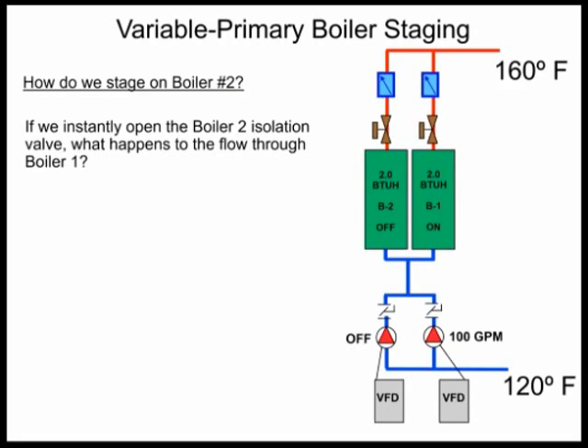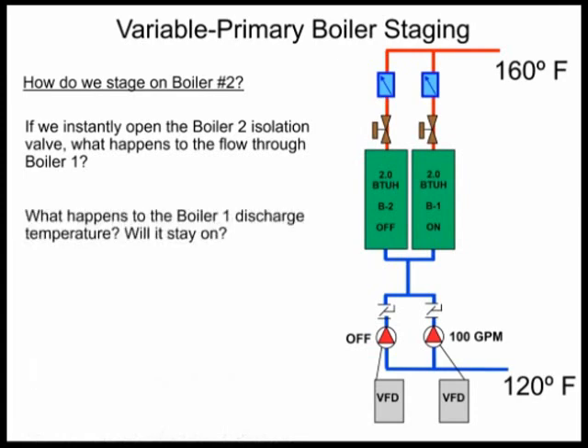If it trips its manual reset high limit, someone's going to have to drive down to the job site and push that reset button. Meanwhile, your owner is going to have an inoperable boiler and comfort issues. What happens to boiler number one's discharge temperature if you stroke that valve open quickly? It very well might go beyond the limits of the boiler and you may have serious problems.